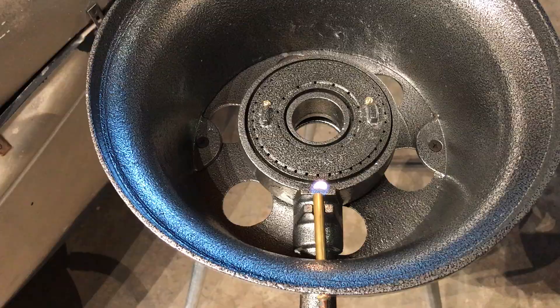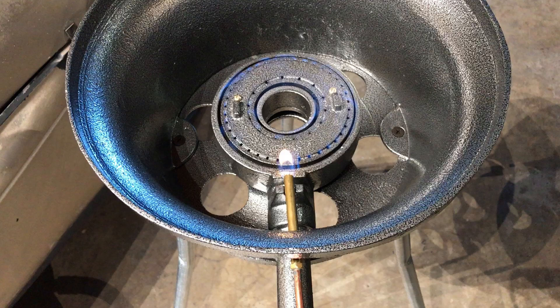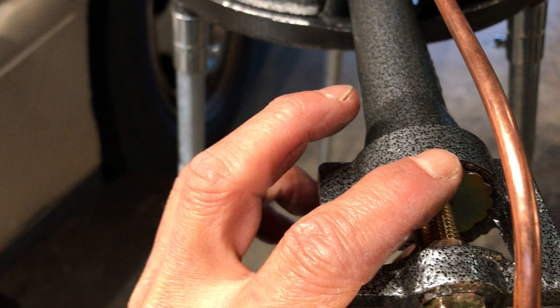Sometimes you may get a yellow flame. The flame is not strong — not strong at all. The reason for that is this air and fuel mixture wheel is too tight into the burner.